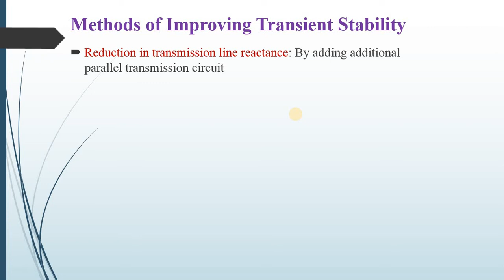Next is high speed fault clearing. In general, two cycle breakers are used in locations where a fault must be removed quickly to maintain stability. But as the time of fault clearing decreases, so does the amount of kinetic energy gained by the generator during the fault. So this will improve the transient stability of the system, as we have to decrease the kinetic energy during the fault.